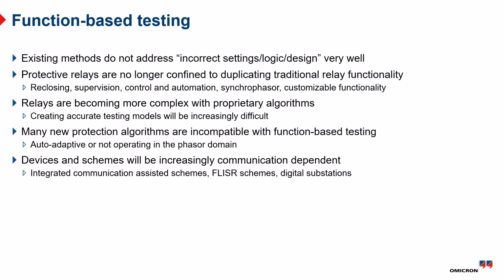I mentioned before, when we started doing testing, the test stimulus we used was not necessarily realistic, and it didn't have to be at the time to verify the element operated. But these new relays are getting smart enough. They know when something doesn't make sense, and the relay isn't actually going to operate the way you expect. Talked about that one. And then at the bottom here, devices and schemes will become increasingly communication dependent.